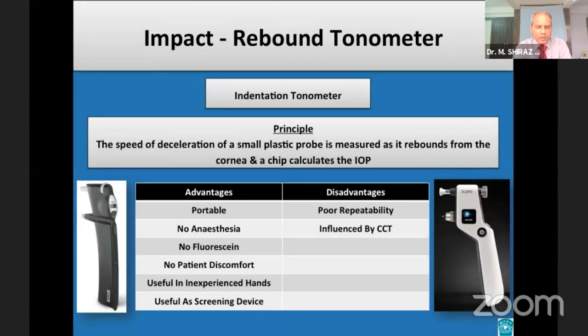Impact tonometry, also called rebound tonometry, in which a lightweight magnetic probe in an enclosed shaft is propelled towards the cornea and the rebound characteristics of the probe are measured, has shown quite some promise.